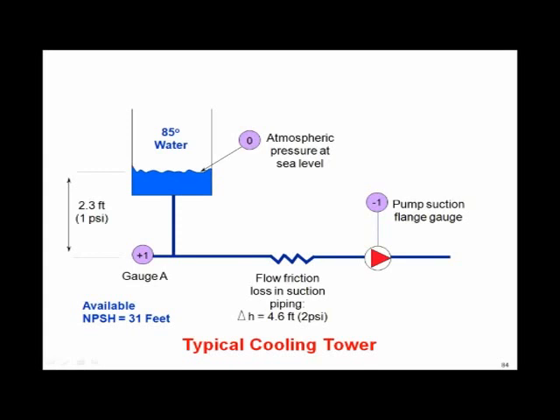Got that one? Now, I got gauges underneath the tower and a gauge at the pump. Let's turn the pump off. So with the pump off, what would those gauges read? With the pump off, I got elevation 2.3 feet. I've got a gauge reading positive 1 pound. And the gauge on the suction side of my pump with the pump off is going to read a positive 1 pound. Now what happens when I turn the pump on? Well, I got this friction loss of 4.6 feet. By the way, I think everybody knows this: 2.31 feet makes a pound of water, specific gravity 1.